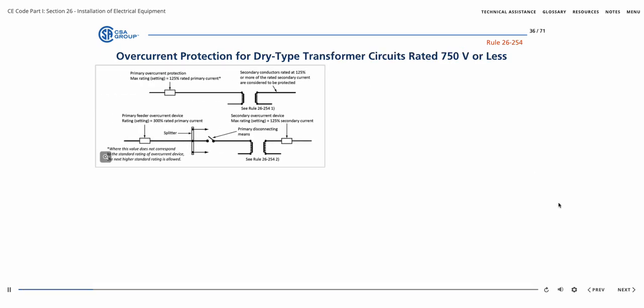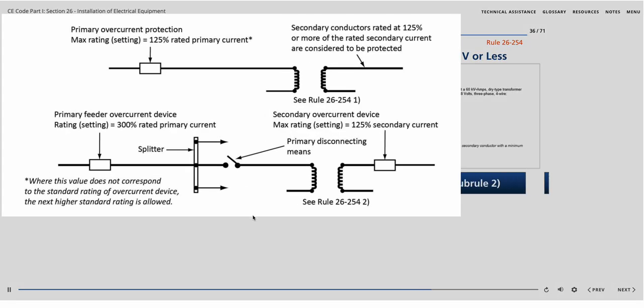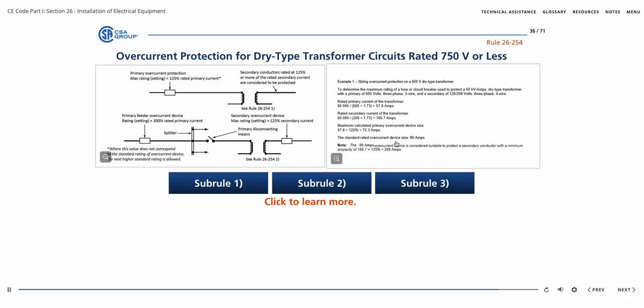Dry-type transformers usually do not have the overload capacity of dielectric liquid-filled transformers. As a result, Rule 26-254 describes each requirement for overcurrent protection. Take a look at the example.